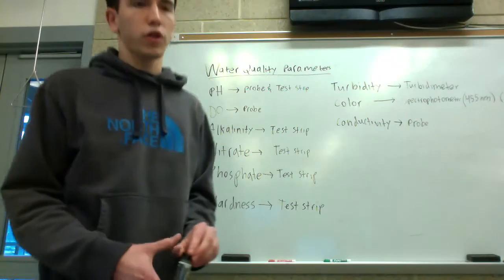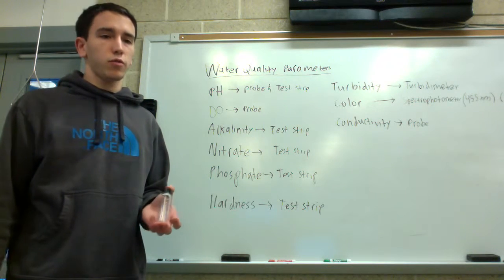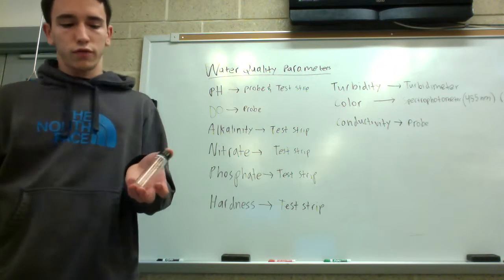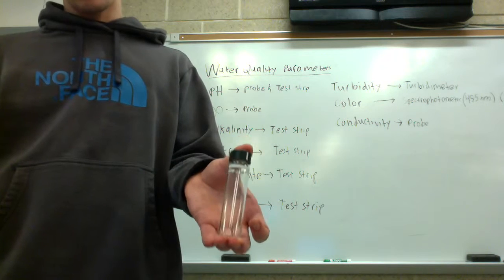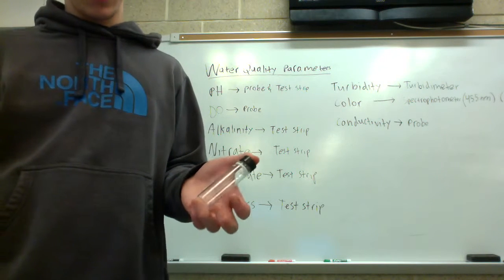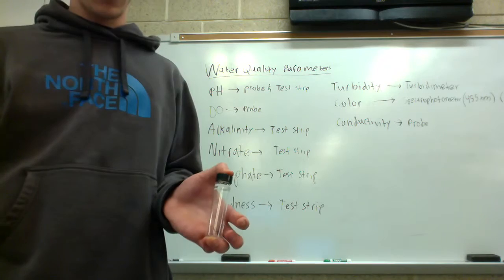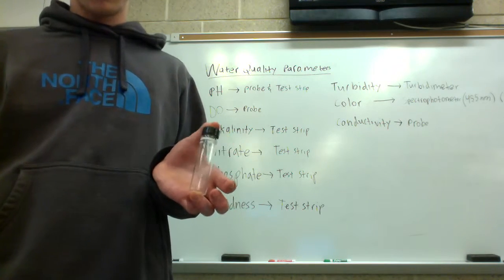For this lab you'll take this measurement using the turbidimeter. Add your water to the sample bottle. Make sure there are no oils from your skin on the outside. If there are, wipe them off with a rag.